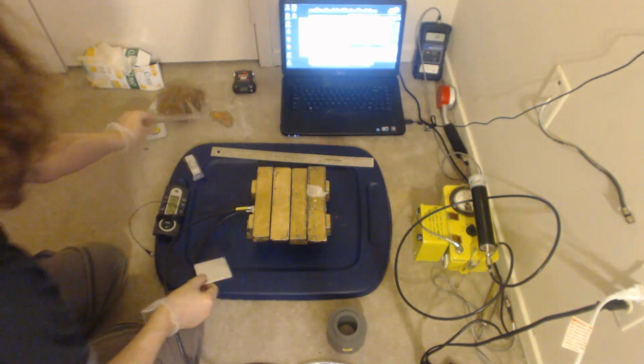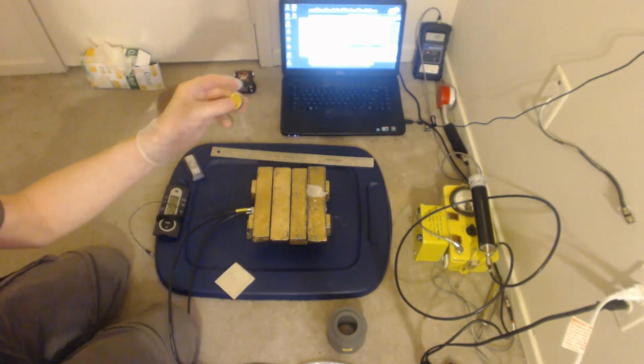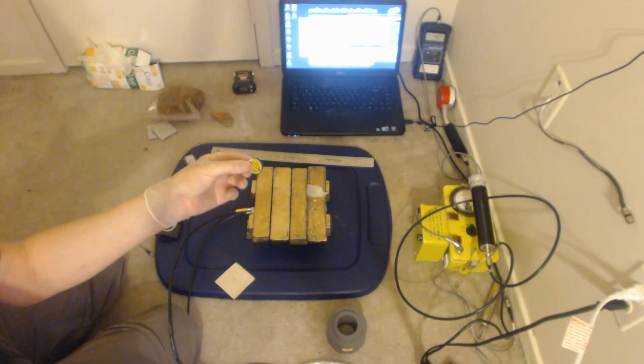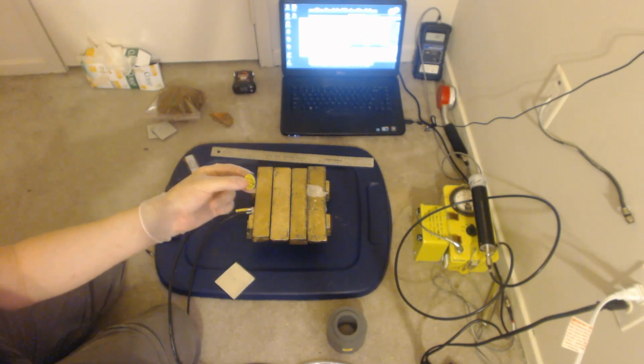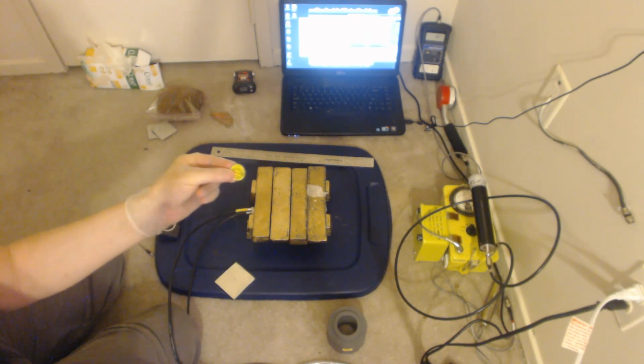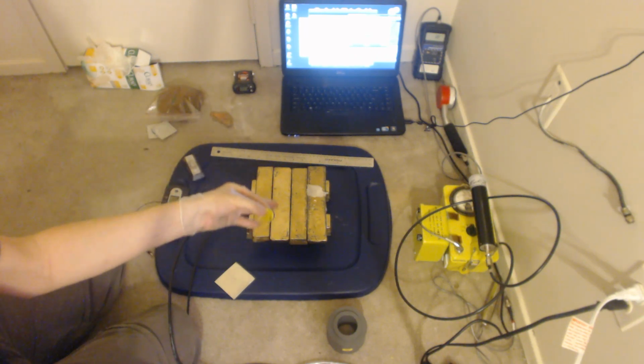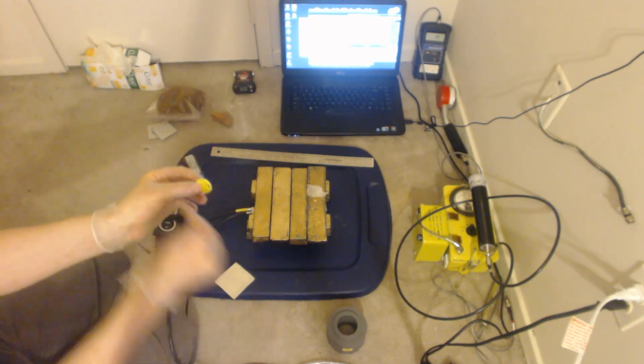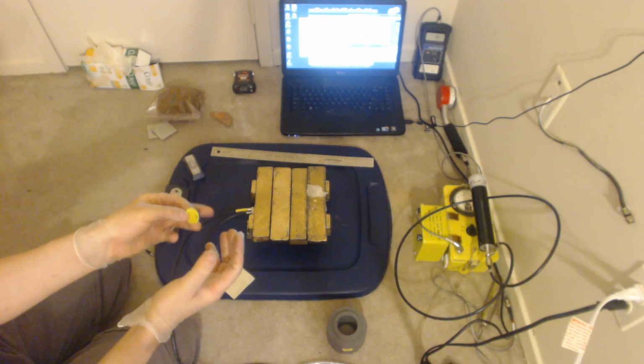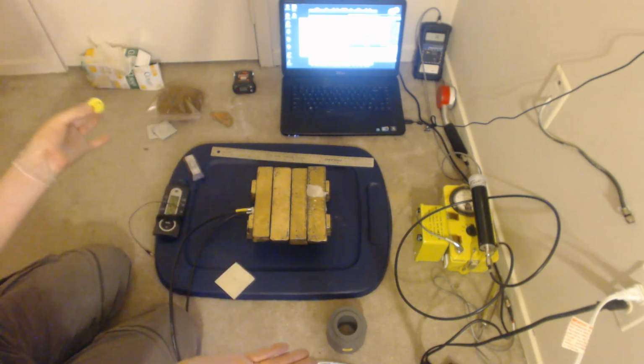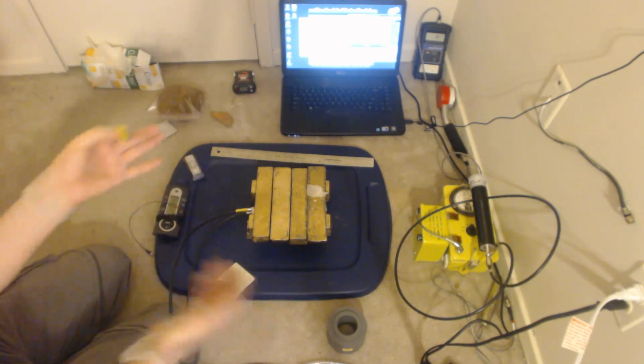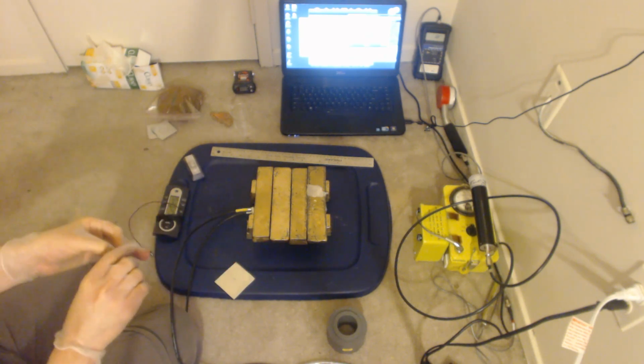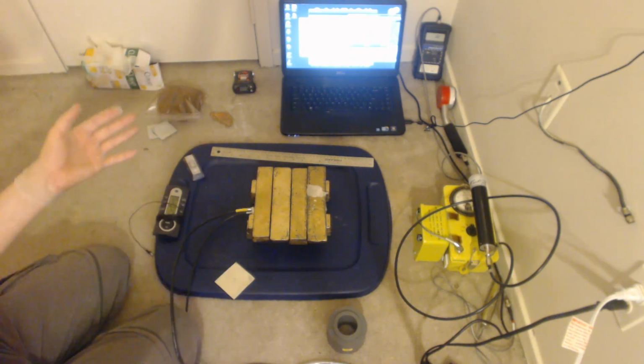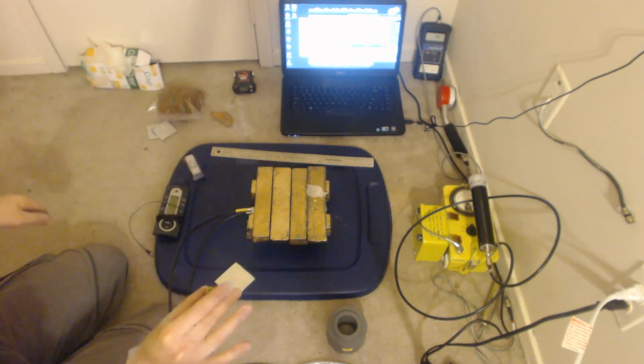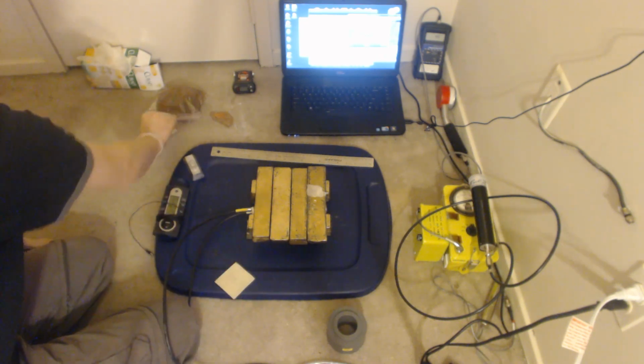Now, you might have been asking, what's this for? Well, things like cesium here produce gamma rays, but they also produce beta rays, and also there's things like beta particles. And there's also things like alpha particles. These particles aren't directly detected by the detector, but what happens is when they hit the metal in the detector, they slow down rapidly, and all that energy of slowing down has got to go somewhere, right? Energy is never created or destroyed. It's just changed. And so that energy gets converted into X-rays. You get all these little X-rays all over the place, drive you absolutely nuts.